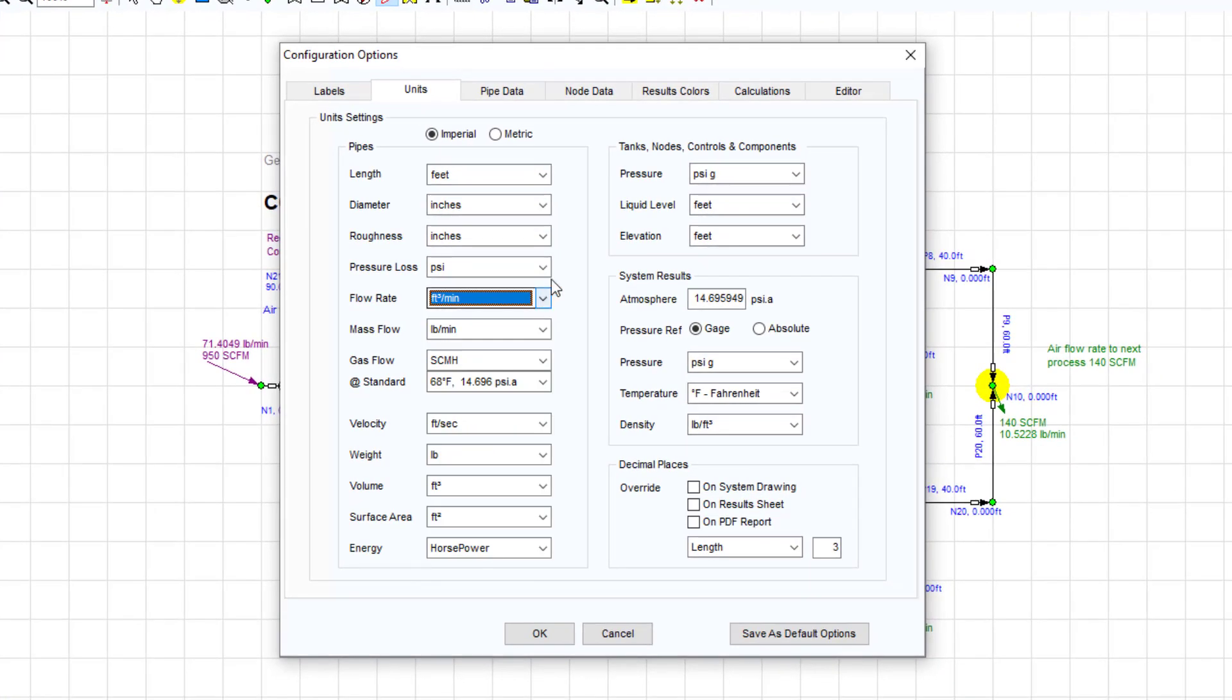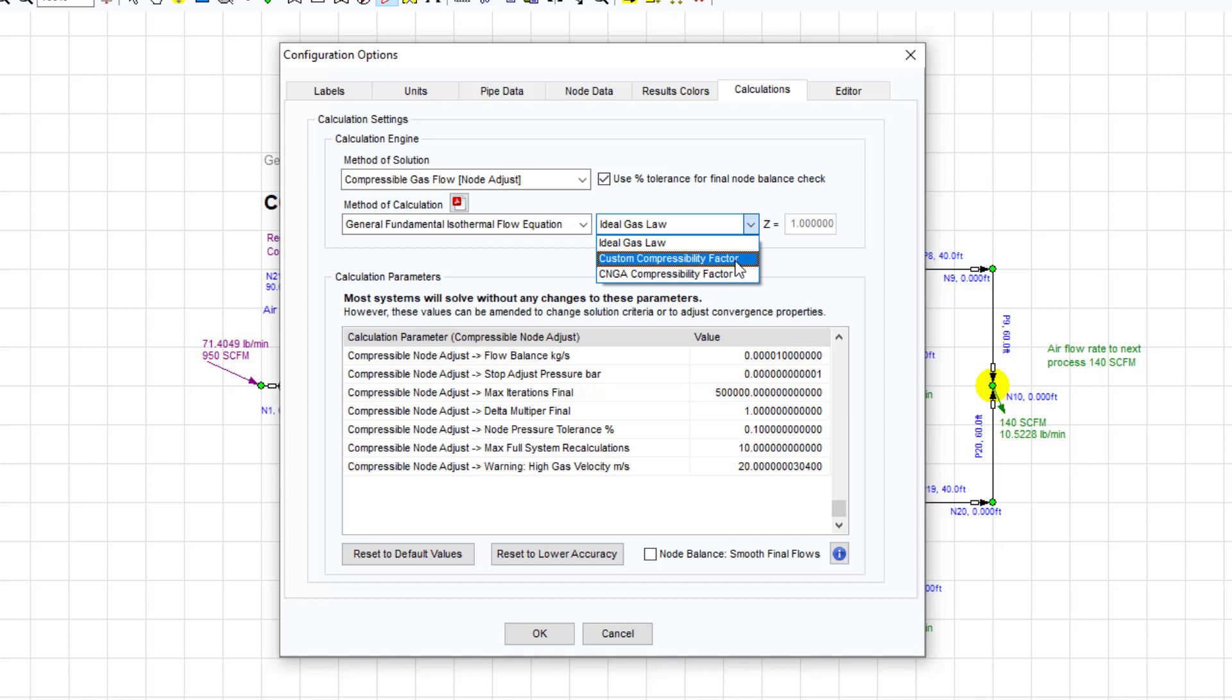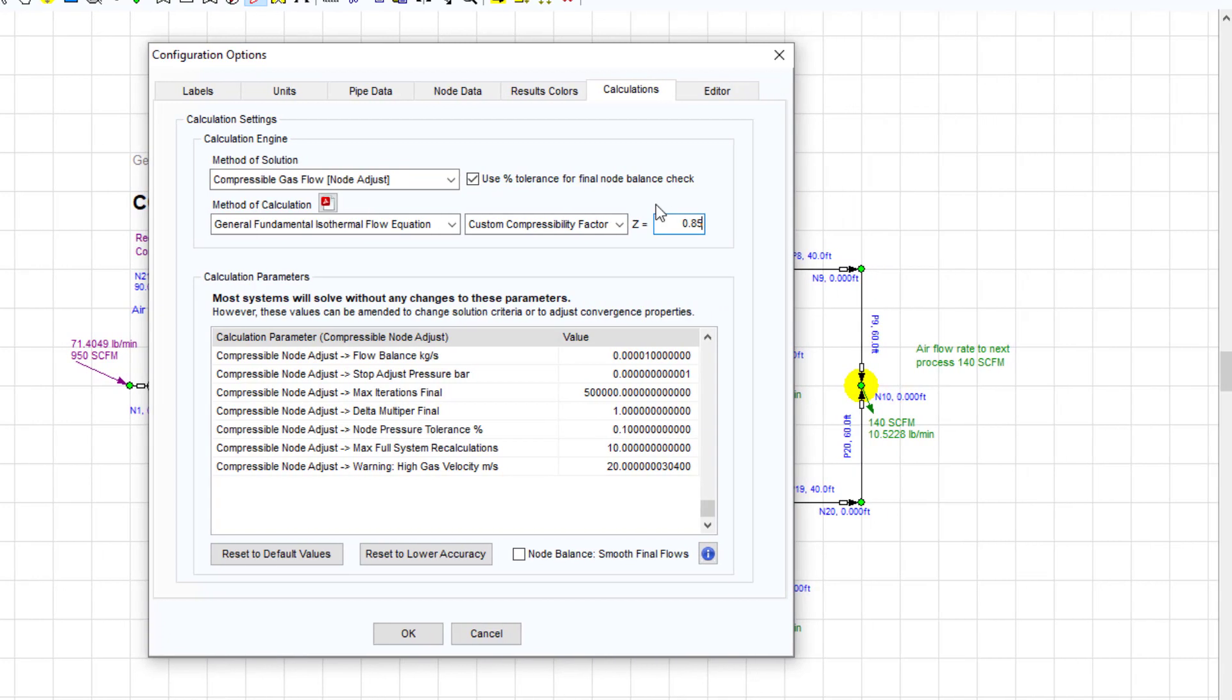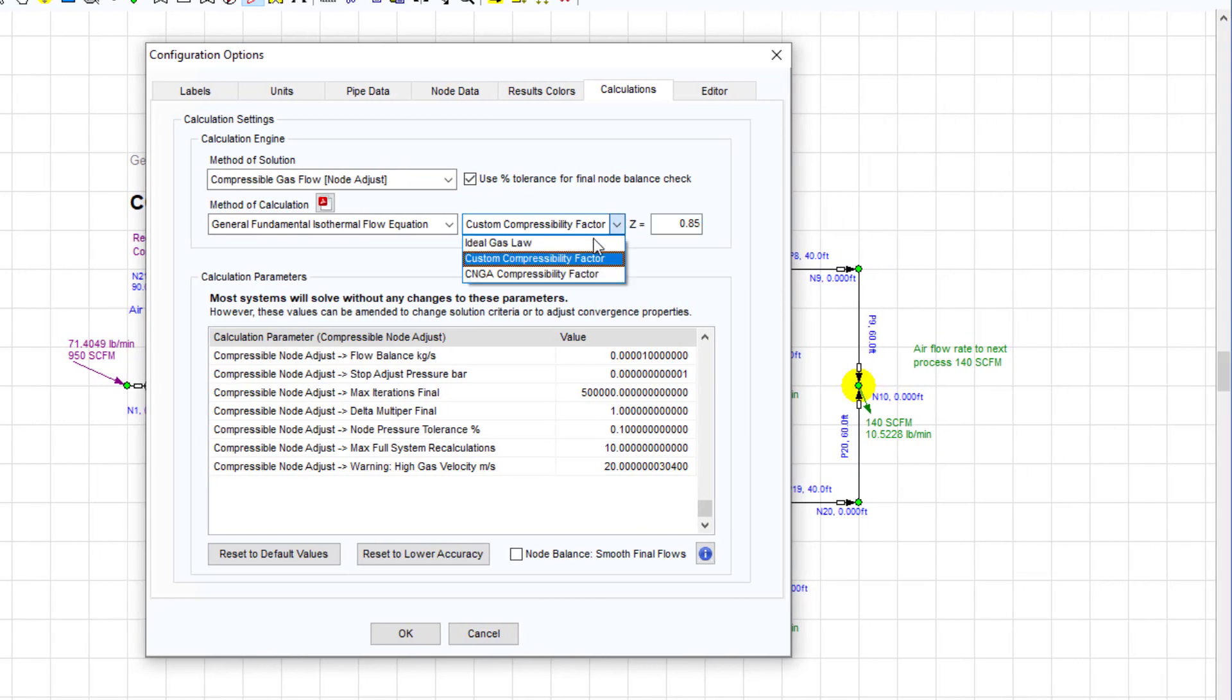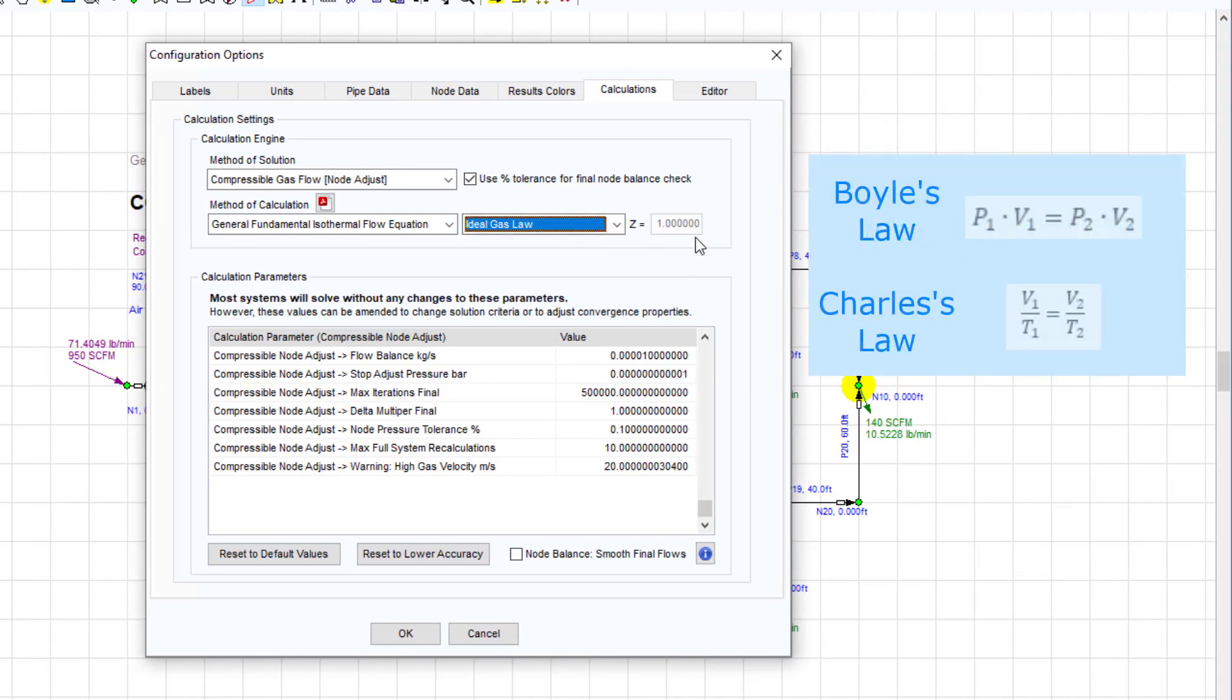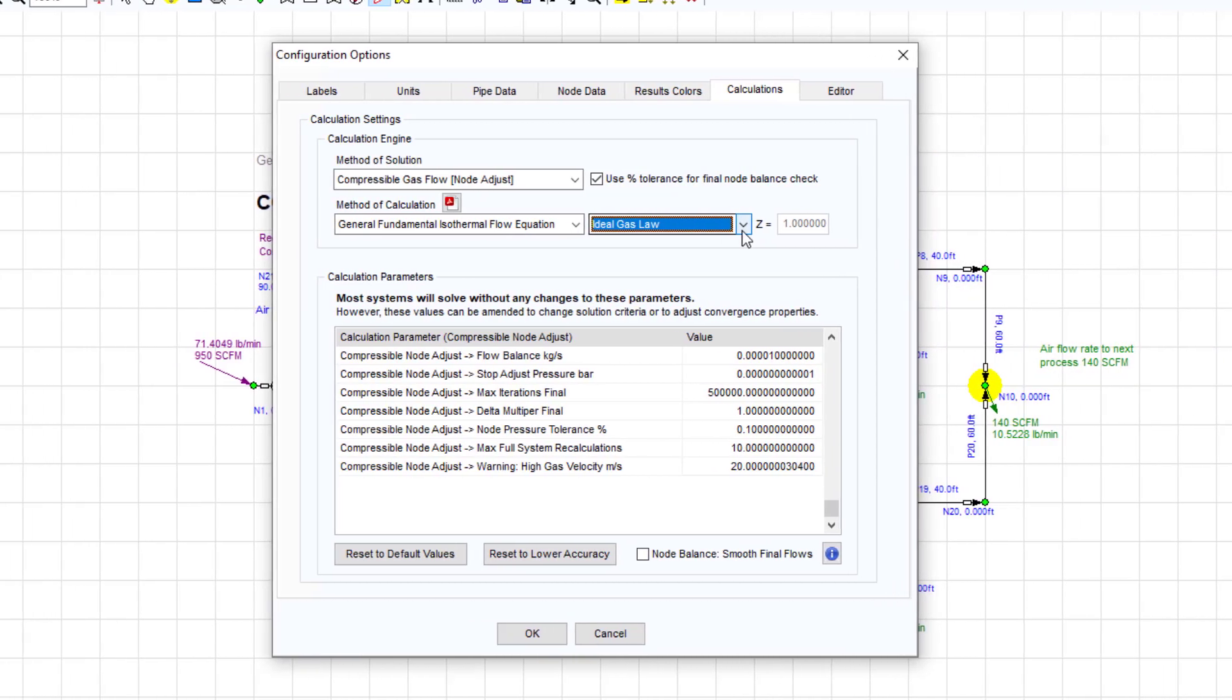The software will automatically convert to show gas flow units using the ideal gas law, or the real gas law if a compressibility value for the gas is specified. Ideal gases follow Boyle's law and Charles' law, and therefore the gas density at various points in the system can be calculated using these equations.